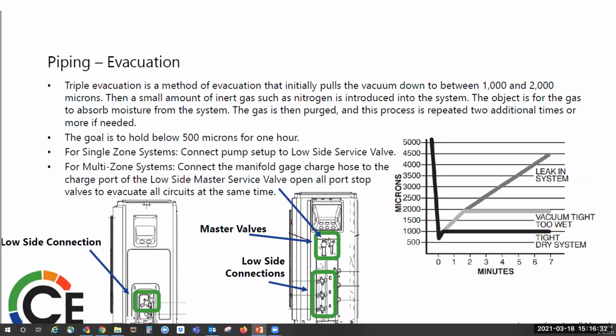For a single zone connection, you want to go down here at this port, the suction line, low side port, and on multi-head systems, you want to come up here and attach your gauges to there. And then when you do that, you can open up whichever valves you have, or all of them, whichever ones are connected to the indoor units. And you will have to allow time for each circuit to pump itself down.